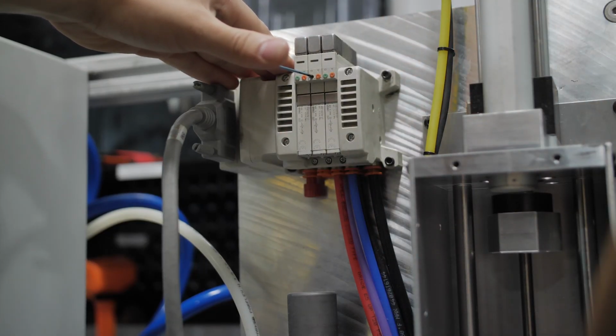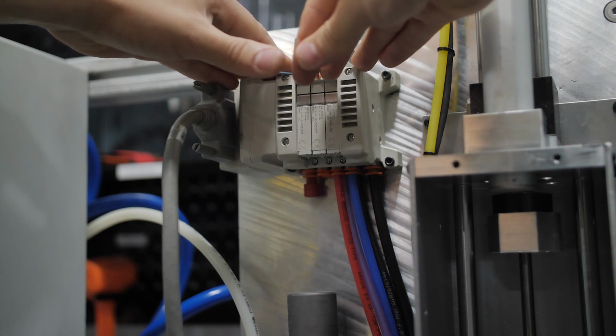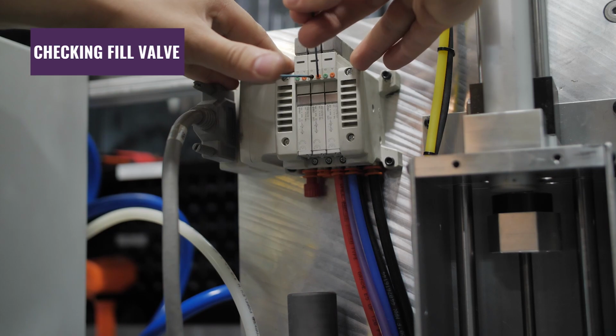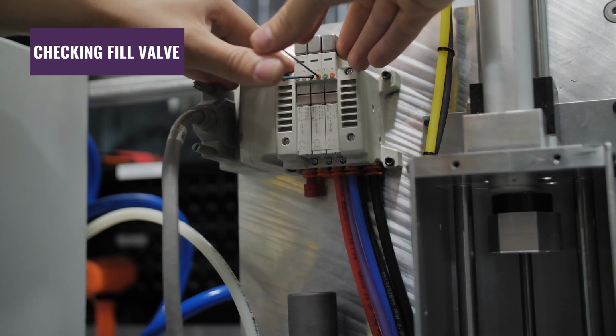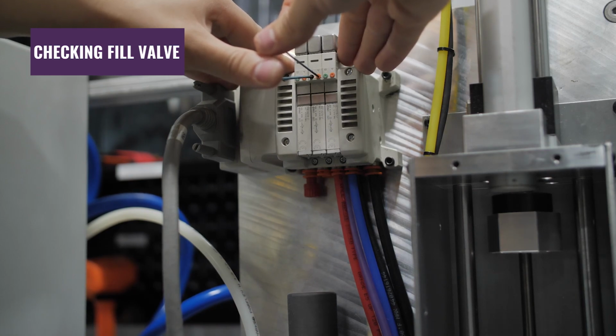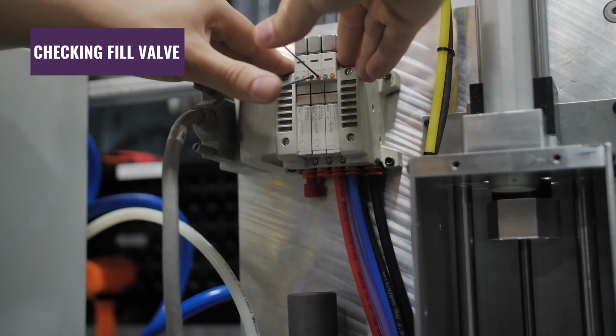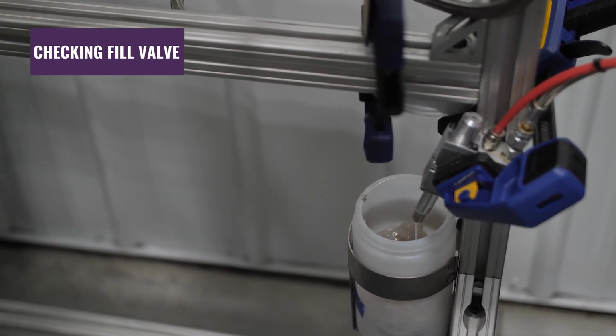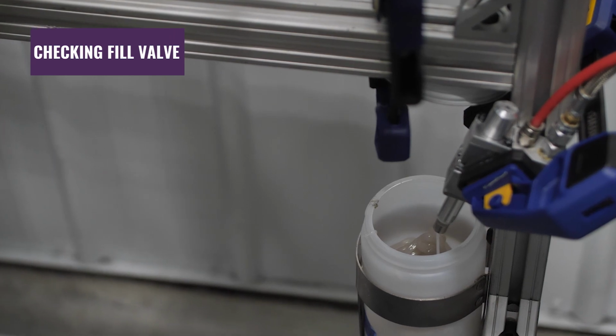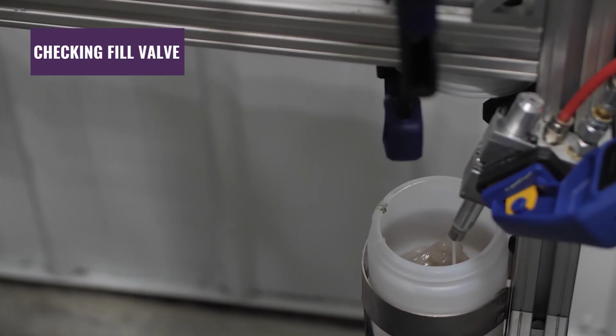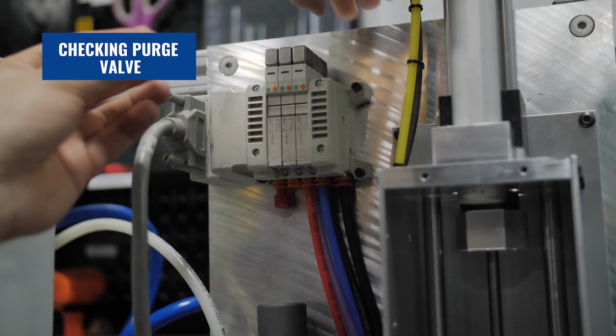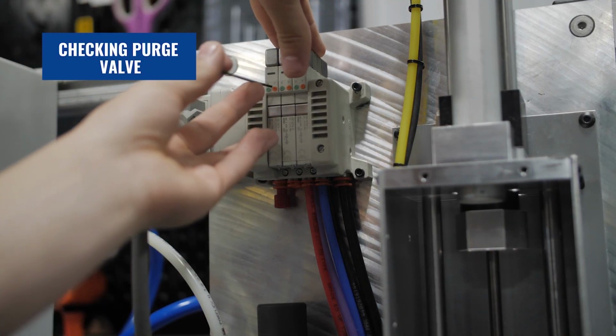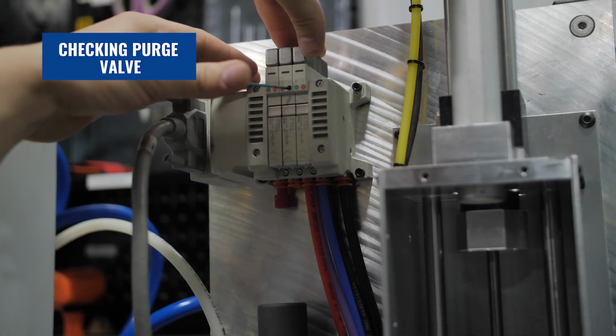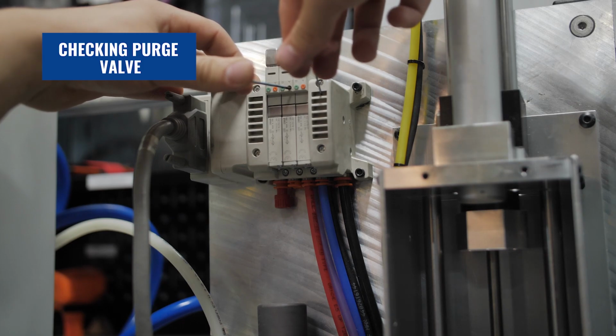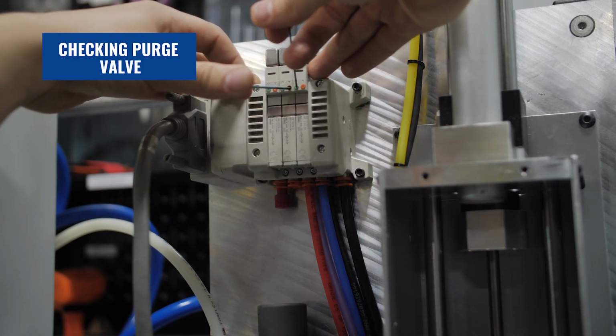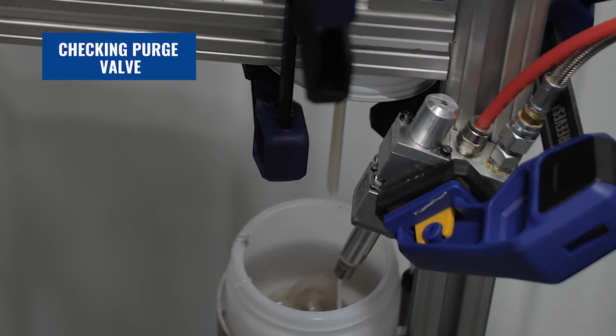I'm holding open the dispense valve, and if I toggle the fill valve, it will fill the chamber with material and will come out the dispense valve right away. And this is checking our fill valve. And we can see from the DV down there that it is coming out. Red, which is dispense, is open, and we toggle fill on and off and make sure that it's going when it's going. To test the purge valve, we hold open the fill valve and we cycle the purge valve to make sure that it's working properly. And as you can see, it is coming out of the purge line into the purge can.